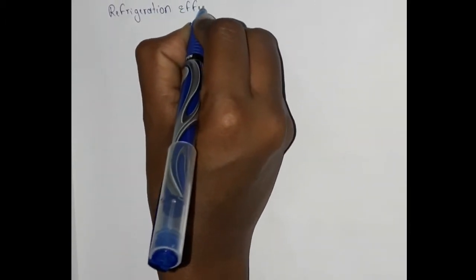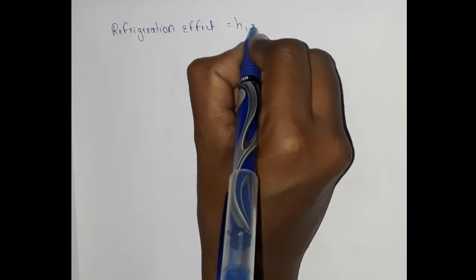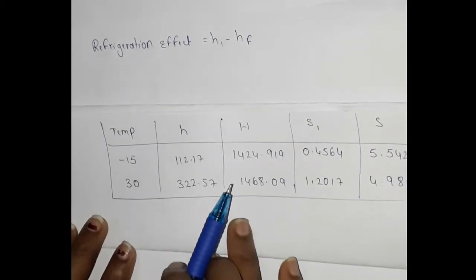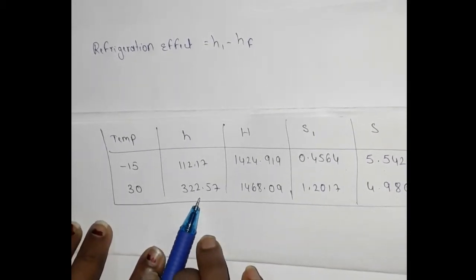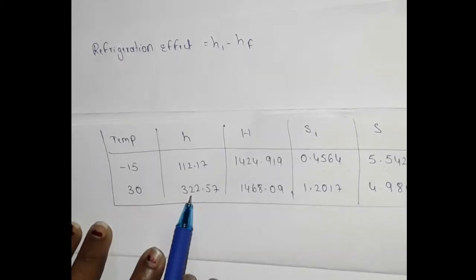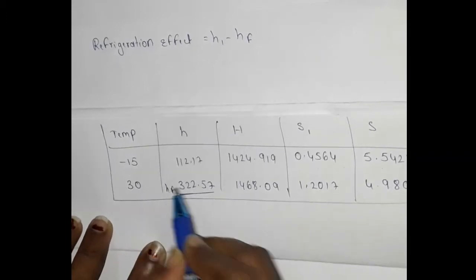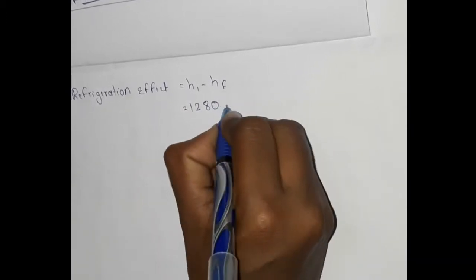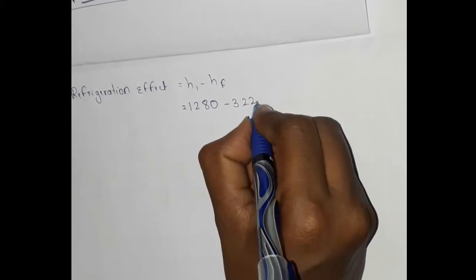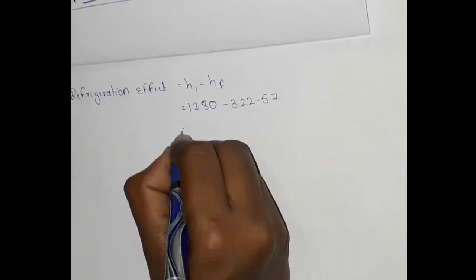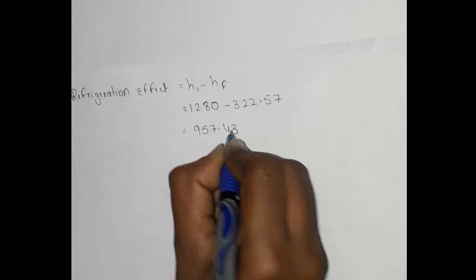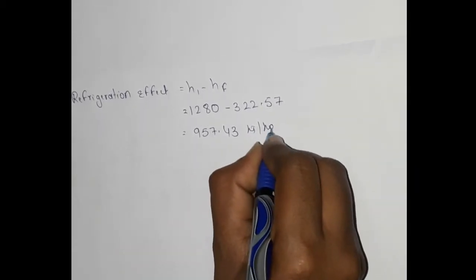The refrigeration effect formula is H1 minus Hf2. H1 is already found as 1280, and Hf at the second temperature (30°C) is 322.57. So refrigeration effect equals 1280 minus 322.57, which equals 957.43 kilojoules per kg.